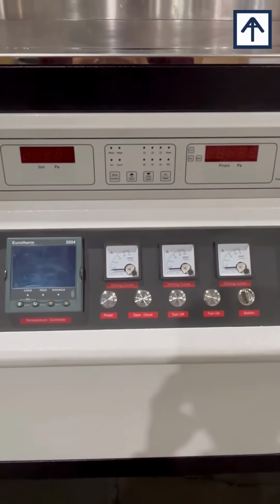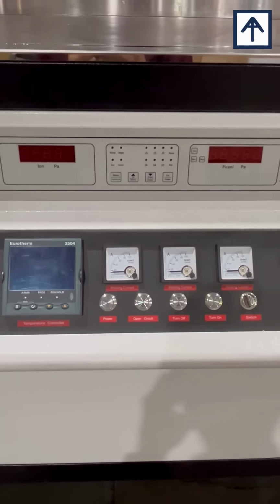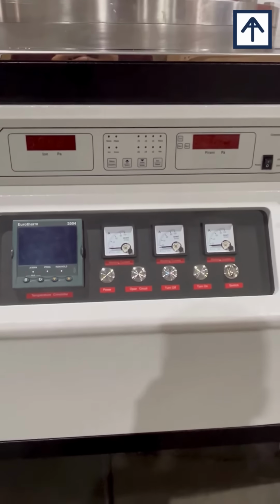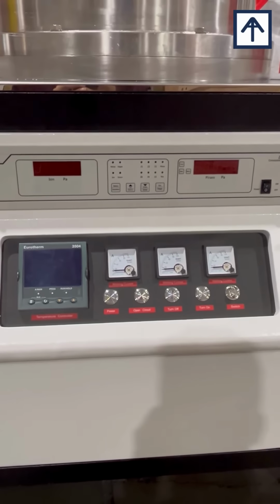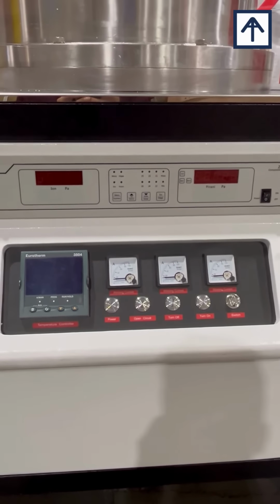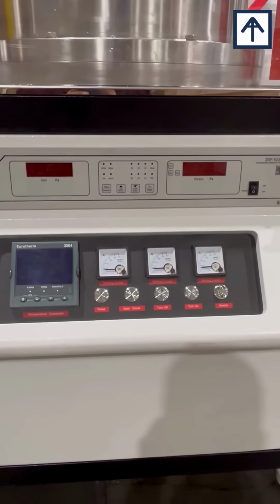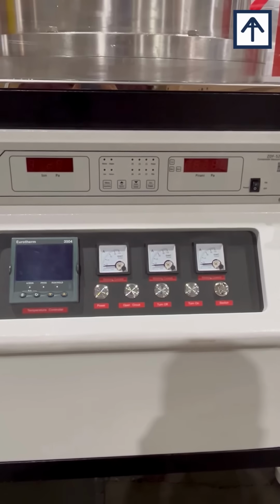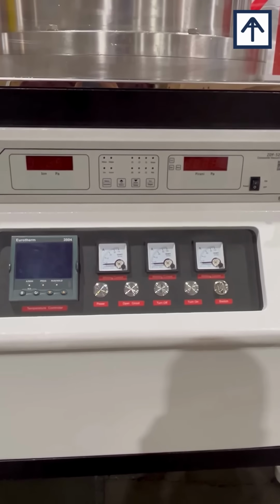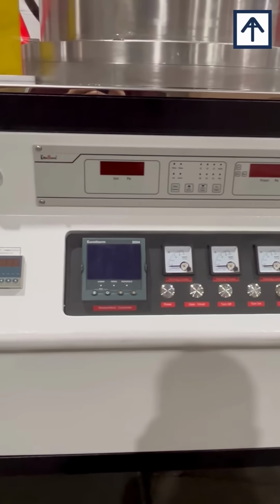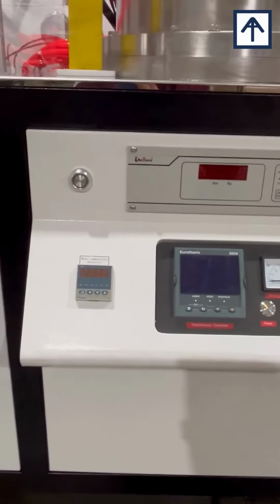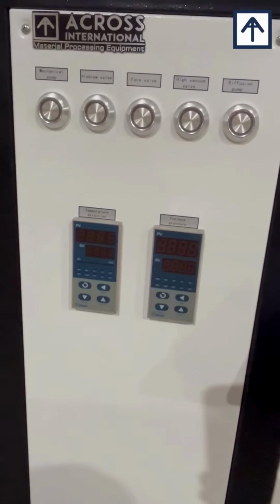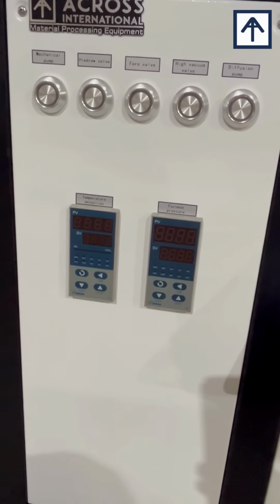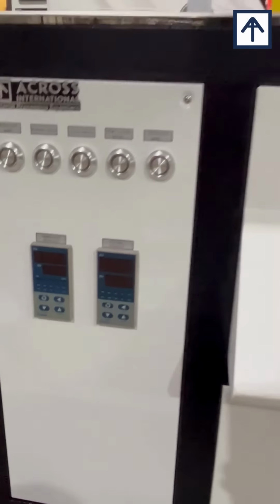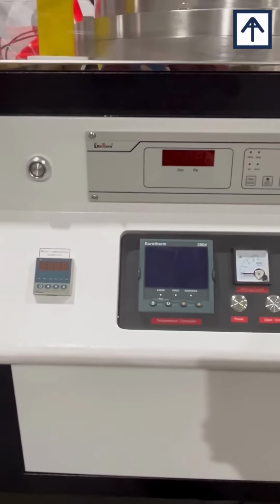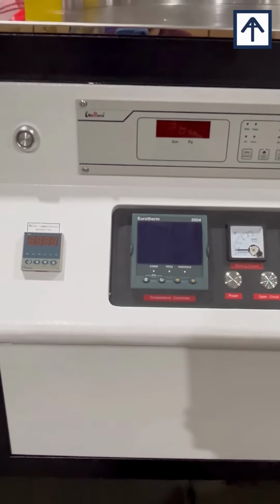The 3 ammeters that you can see are for your amps from each of the lines, which this unit is a 480 volt 3-phase. And then on the top you have your vacuum sensor, which, as you had mentioned, is the vacuum sensor on the back of the unit. That senses the vacuum for ultra deep level of vacuum, which is used by the turbo pump or the diffusion pump for the system, based on the applications that you need. And then we also have a secondary temperature sensor detection on there, which tells you the secondary temperature. So if the primary one is damaged, the secondary one would take over the unit itself.